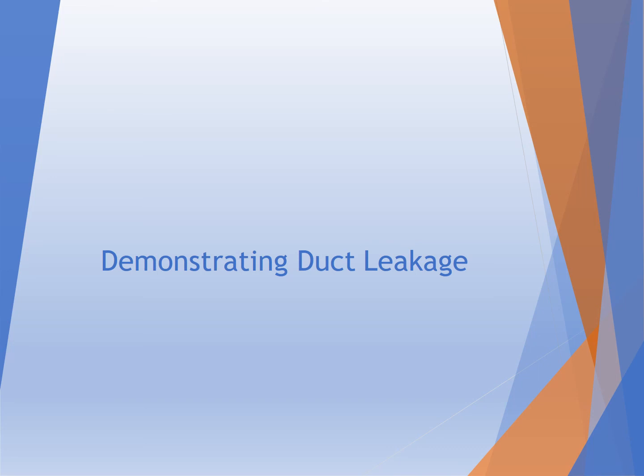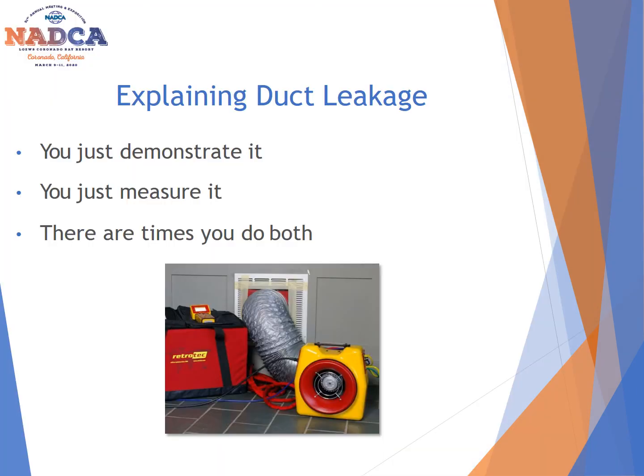Over the next few slides, we're going to take a look at how you can actually demonstrate duct leakage and show your customer that they may or may not have a problem. I will tell you that there is no magic bullet to the exact way that this needs to be done, but you do need to be able to demonstrate the fact that they have duct leakage and show them that they have it. You need to make sure you have a means of measuring it, and there are times that you'll actually want to do both, and we're going to take a look at a few of those options.